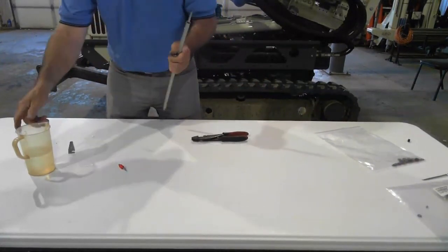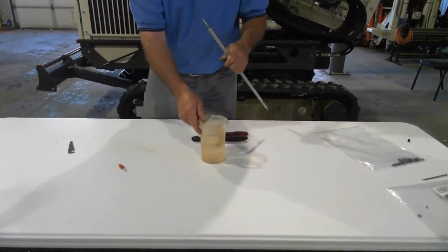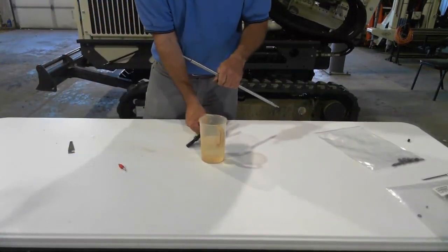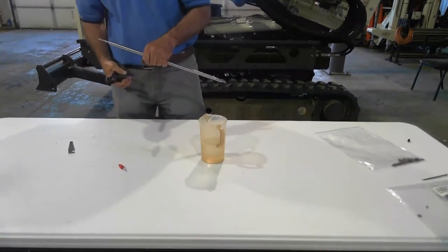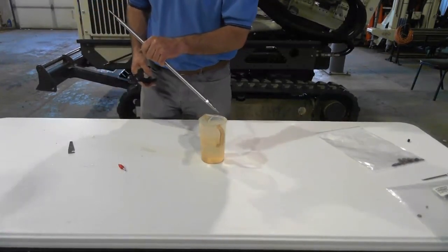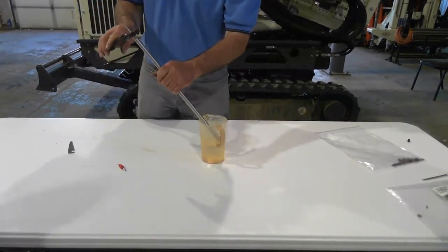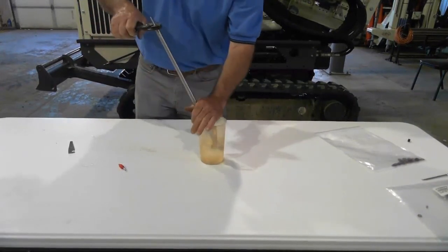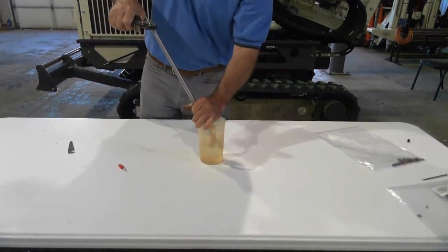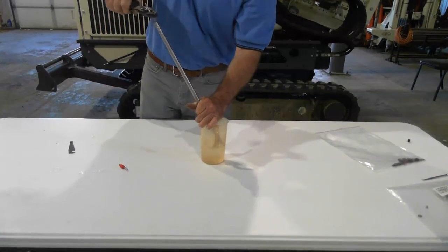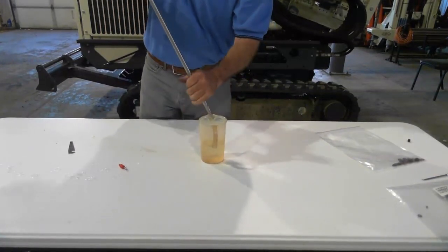The final step is to make sure that the pump is fully operational. We will insert the lower section into a cup of water and actuate the upper side of the pump to verify that it will pump water from the cup. It will be easier to grab the upper barb section with a pliers or a vice grips to do this. The pump works, and it is ready to install onto the probe.